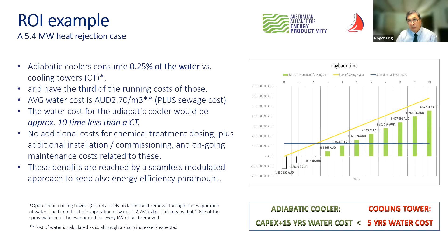Thank you, Roger. And we want to present a few cases where adiabatic cooling or an adiabatic cooler was the choice. Here we are in the field of a waste to energy plant, a plant which is based in the Middle East, where we are required to work on the cooling side of a turbine, lube oil cooling, as an indirect system where the challenge was to reduce as much as possible the water consumption.